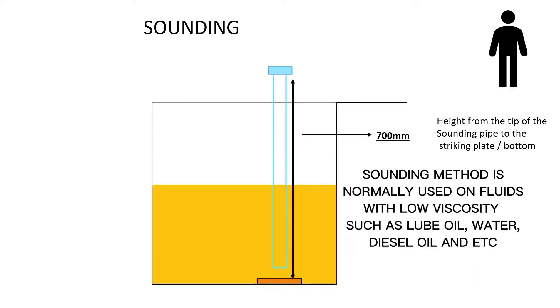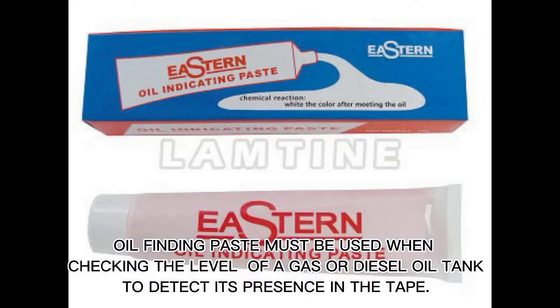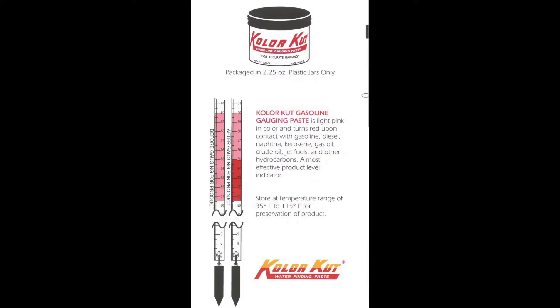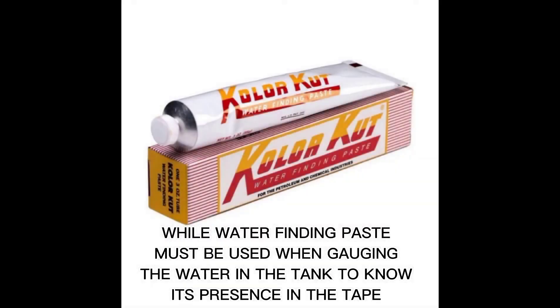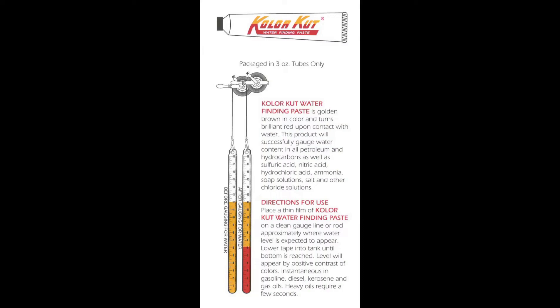Sounding method is normally used on fluids with low viscosity, such as lube oil, water, diesel oil, etc. Oil finding paste must be used when checking the level of a gas or diesel oil tank to detect its presence in the tape. While water finding paste must be used when gauging the water in the tank to know its presence in the tape.